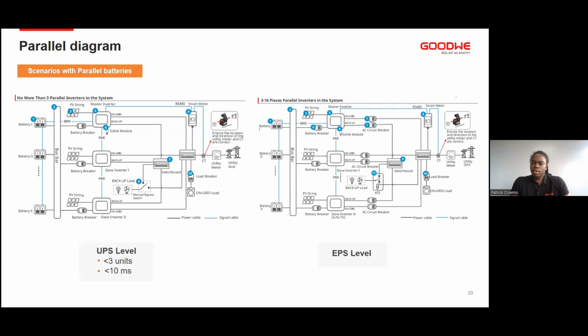If you've done any installation with a single ES Unique piece, future scaling up is possible for designers because you can parallel up to a maximum of 16 pieces of ES Unique in a single system. This is a master-slave topology. Note that the UPS level switching is for 3 installed pieces and fewer. Pieces numbered 4 up to 16, so 4 and above, will achieve EPS level switching.